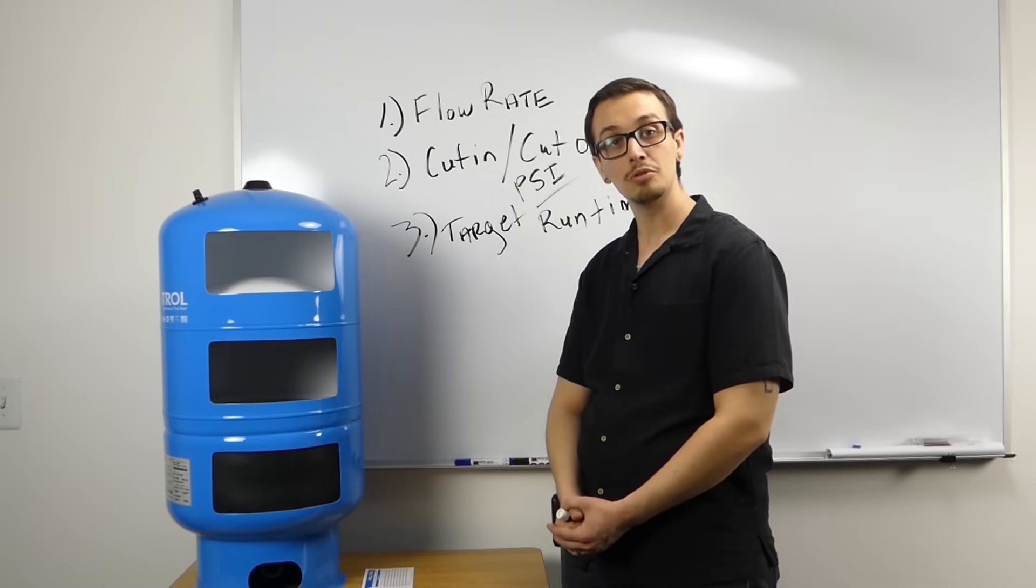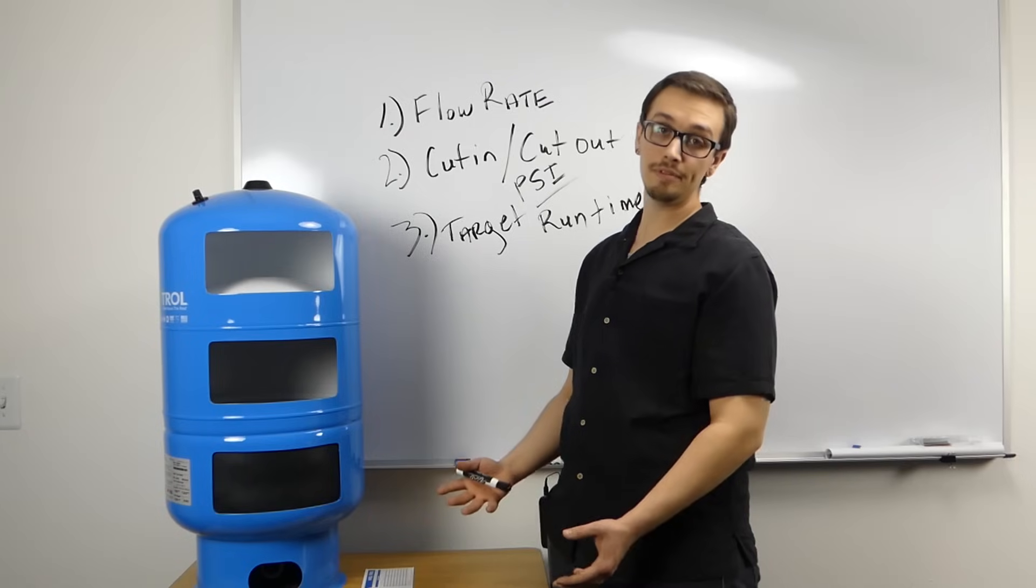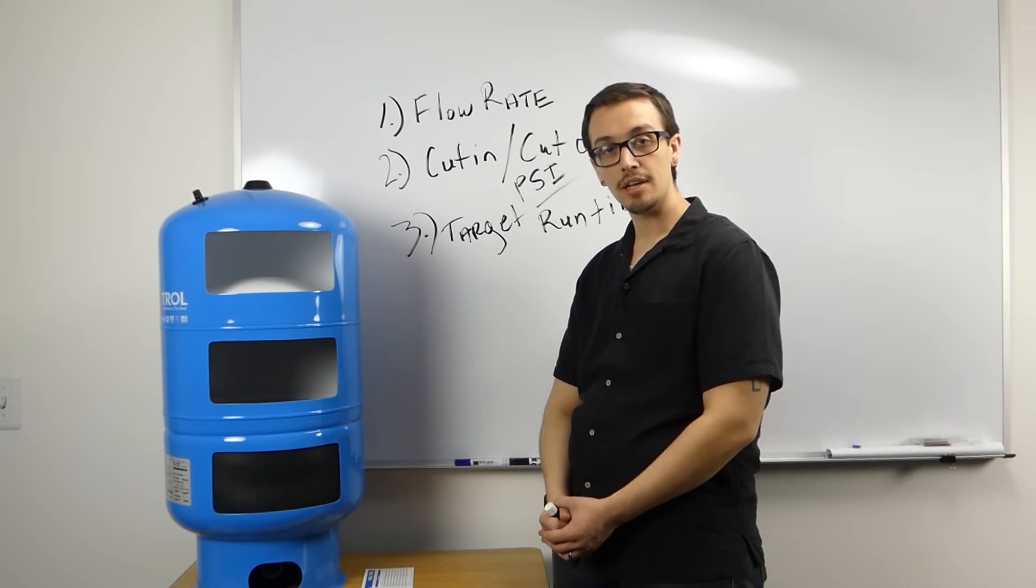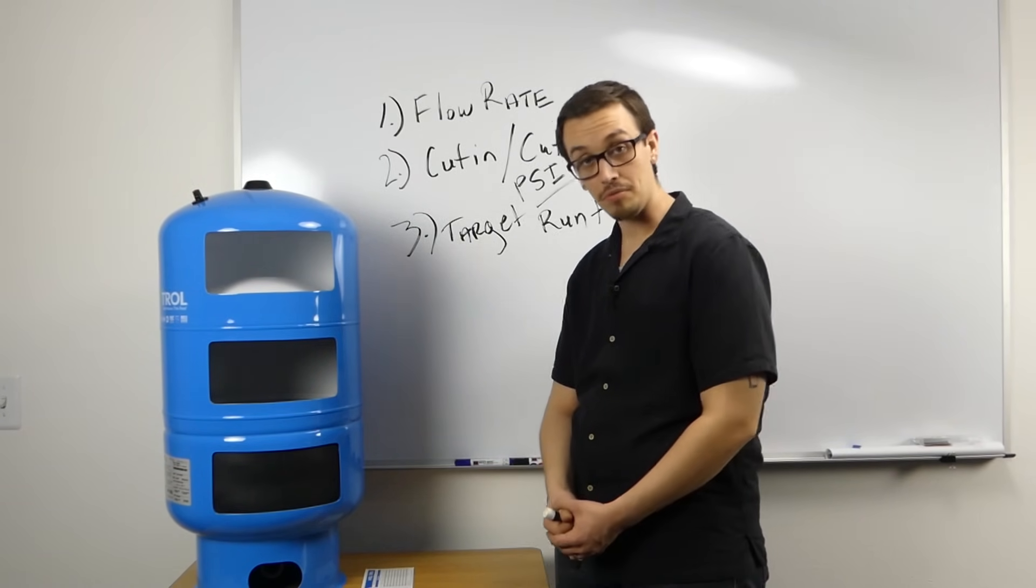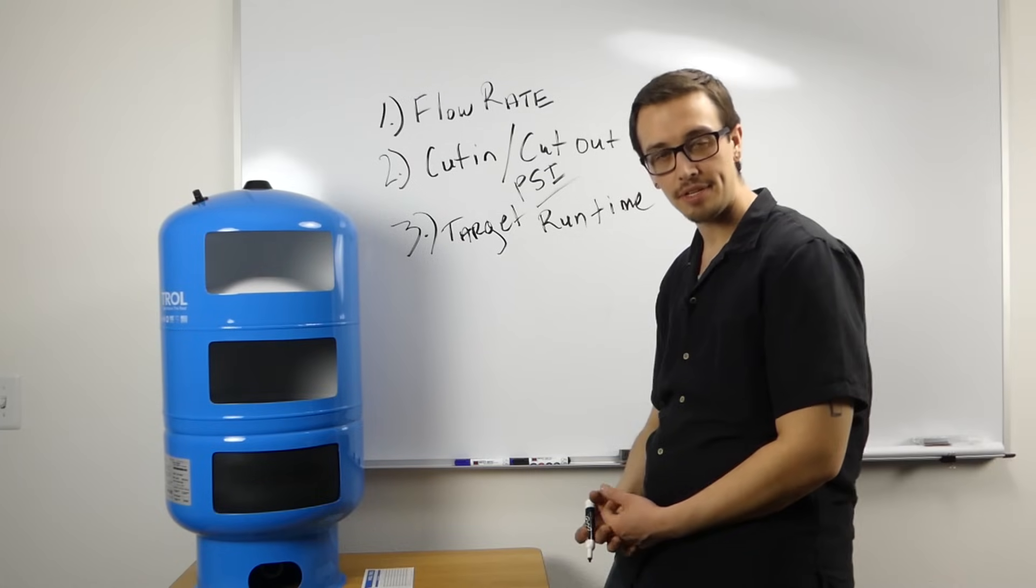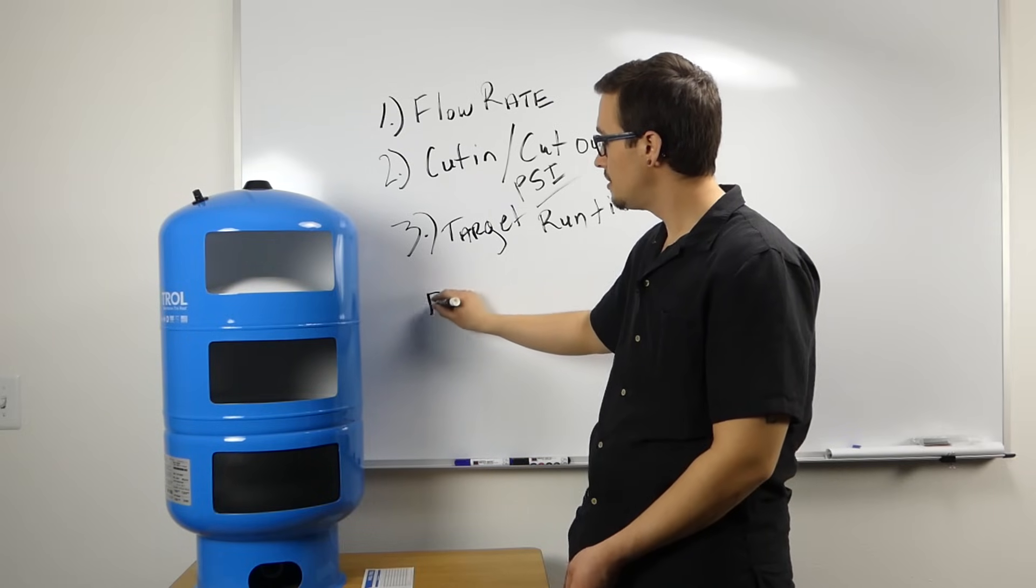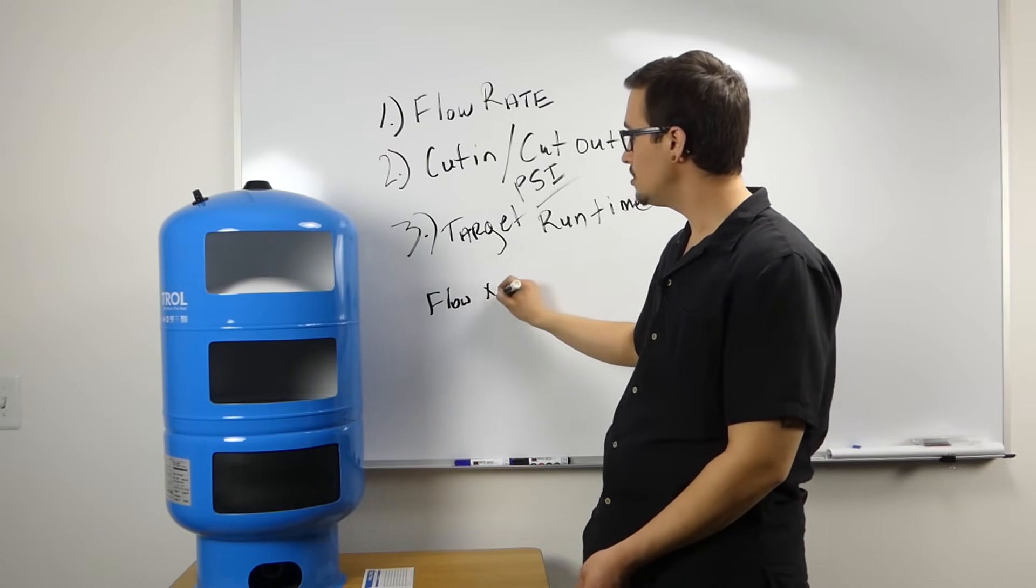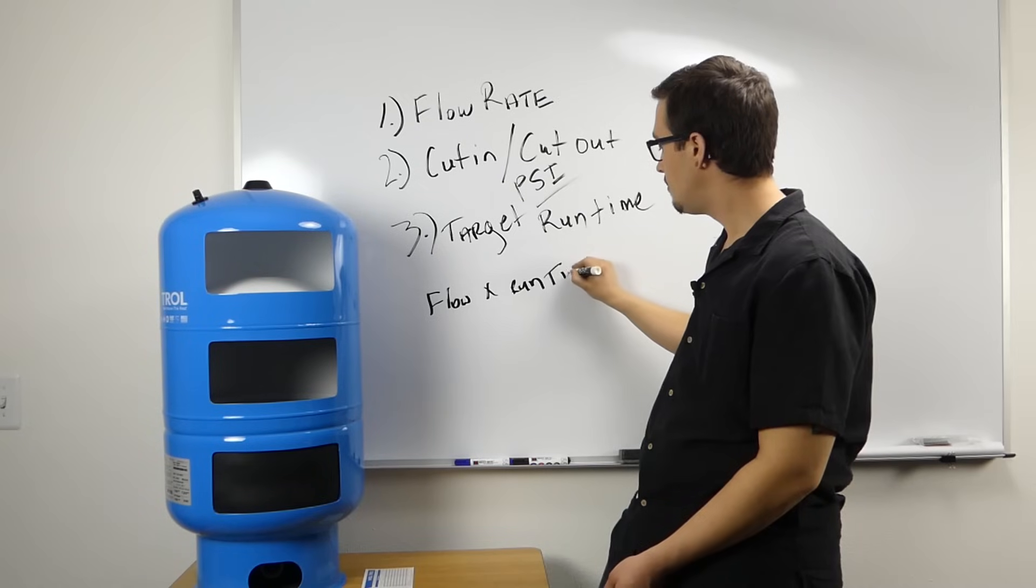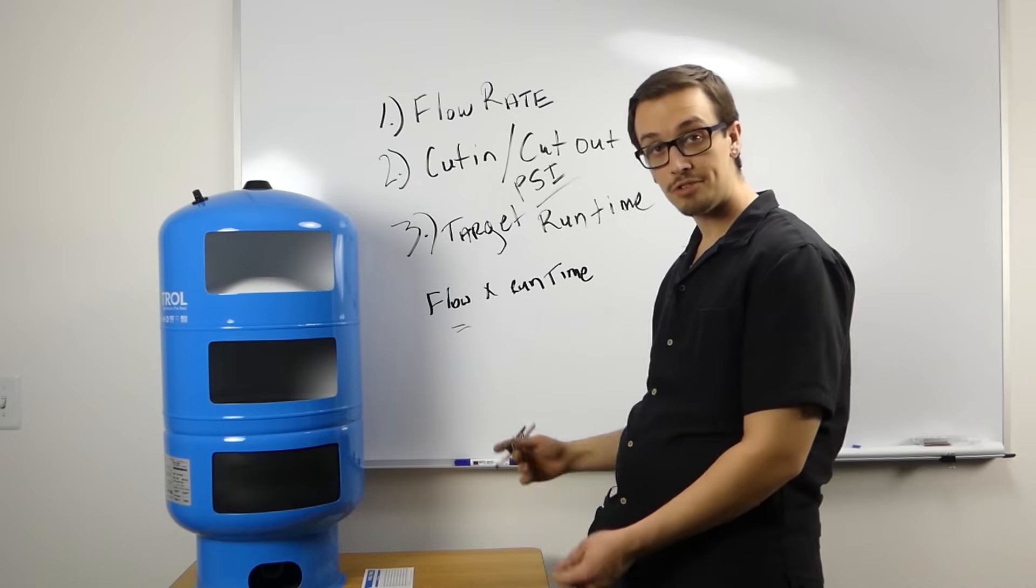As your flow rate increases, so does the recommended drawdown capacity of the pressure tank that you select. As you increase in flow rate, the amount of extra tank needs to increase with it at an even greater rate. An easy equation to help you determine what your tank drawdown capacity will be is to take your flow rate and multiply that by the run time, and you will have the tank drawdown capacity.